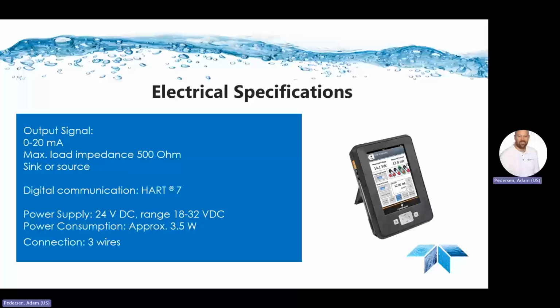Some of the electrical specifications include 0 to 20 milliamps, and that can be in either sink or source. The digital communication will be HART7. The power supply will be 24 volts, and the consumption will be approximately 3.5 watts. The connection is going to be 3-wire as well on this unit.